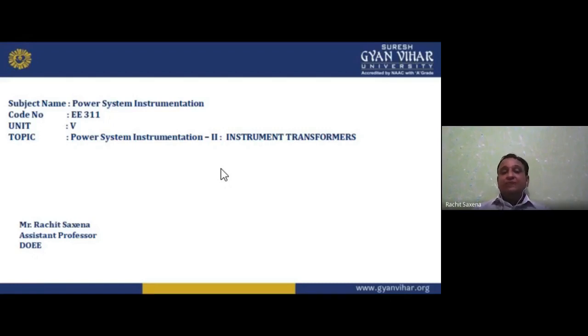Then we have grounding and shielding. Grounding is a very important part. Why? Because if there is a leakage current, meaning a fault, the leakage current will always flow into the path that has low impedance. It is similar to driving a car to a destination: I follow the path with fewer red lights, hurdles, and speed breakers. Similarly, the leakage current will always follow the path with low impedance. So we have to produce a low impedance path.